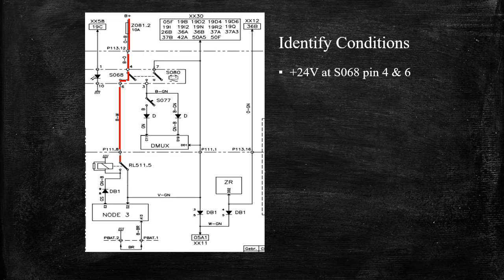So we would check the back of the switch for pin 4. It's a blue and orange wire. That's what the B and O stand for. And then coming out the other end, a blue and white wire, so it has blue with a white tracer. We should have 24 volts. And it goes all the way down to plug 111.6. Looks like 0.6 here, or could be 8. And then it would go through this connector, so we can check here also for 24 volts. We should have 24 volts all the way through.